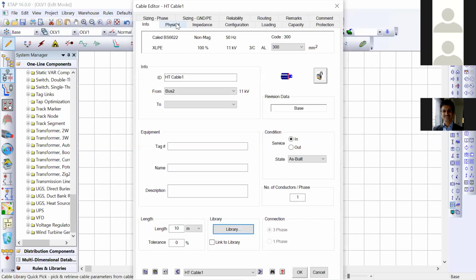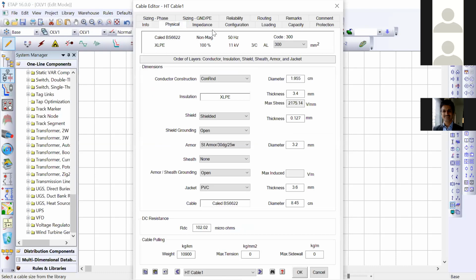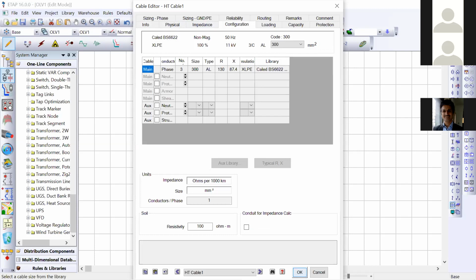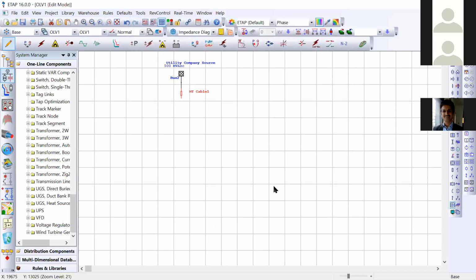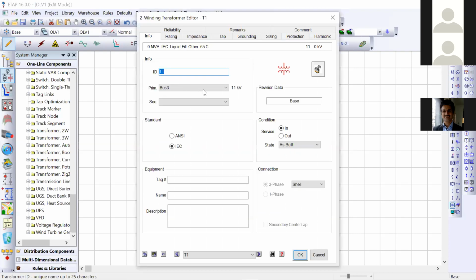The rest of these parameters it will take automatically from its library. I don't need to give each and every parameter separately. So this is done with the HT cable. Now comes my transformer. I'm selecting a 2-winding transformer. I'm connecting the HT cable with the transformer, and now we'll see the transformer is connected on bus bar 3 and it has got a primary voltage level of 11 kV.